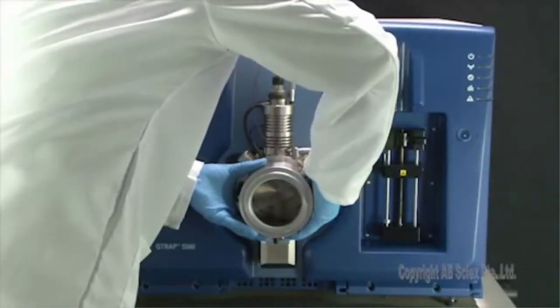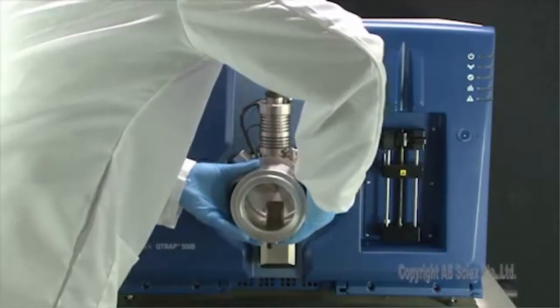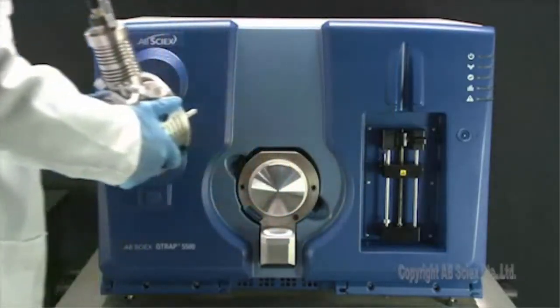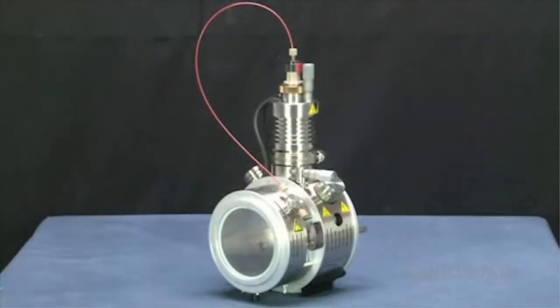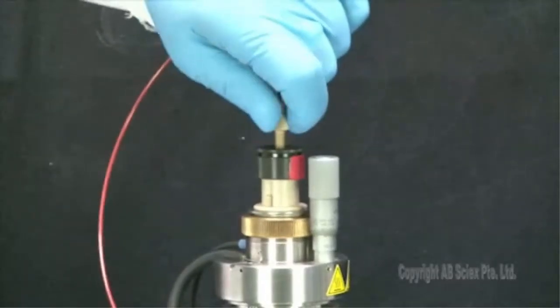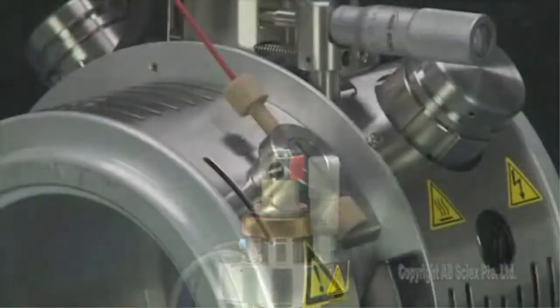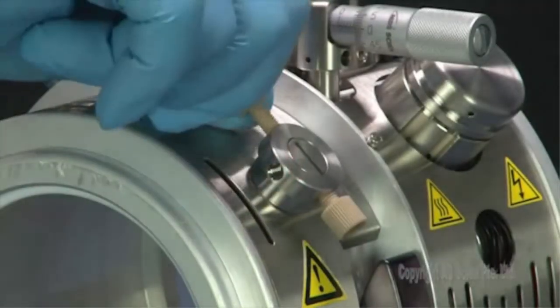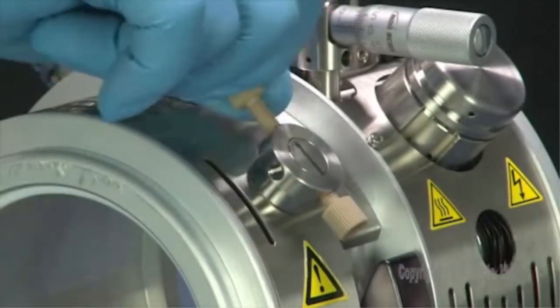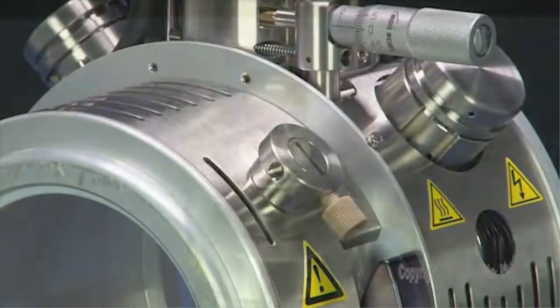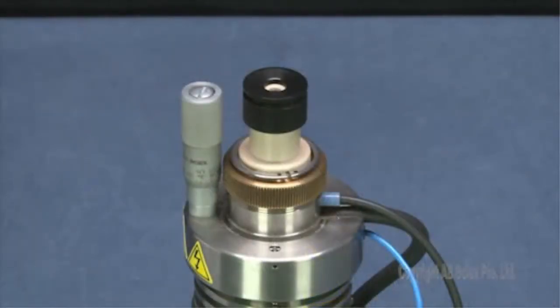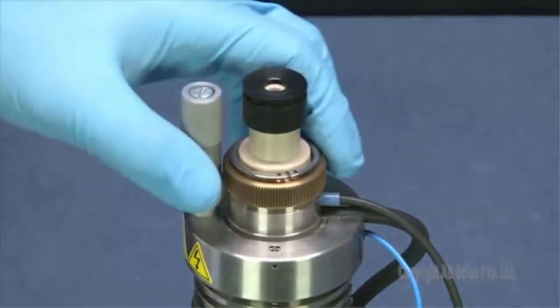Next, firmly grasp the outside of the source with two hands and pull the source away from the mass spectrometer. Place the source upright onto a clean laboratory bench. Loosen the PEEK finger-tight fitting and remove the sample tubing from the probe. It may be easier if the other side of the sample tubing is removed from the grounding union. Loosen the brass retaining nut until it is no longer engaged with the source.